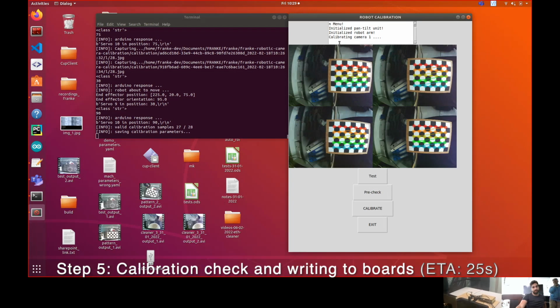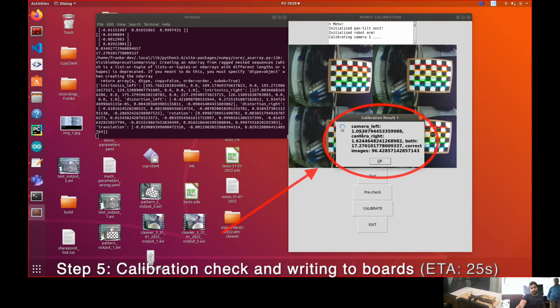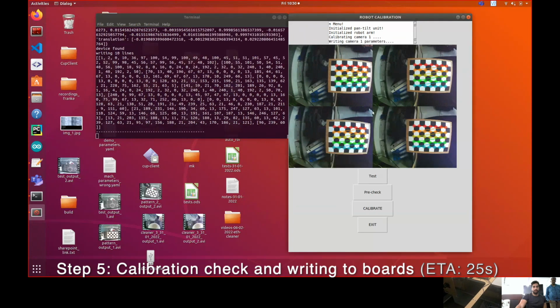I'll just continue here because it says calibrating camera 1 right here. So right now it's calibrating. It gives us around 1. Can you mark the percentage? Yeah, a 1 value of reprojection error for left and right, which is fine. It gives us 96.4% of correct images or correct samples, so that's also good. It just has to be over 85% and should be all right. And for the reprojection error for camera left and camera right, around 1.5, 1.6 is also tolerable. So right now I press OK.